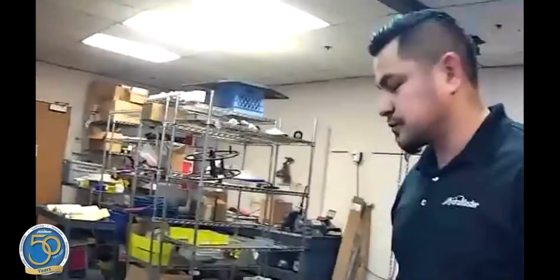Let's talk about some of the reasons why you need to descale. Hard water would be the biggest reason, causing calcium buildup within the system. If your municipal water is higher than 3 grains per gallon, it's recommended to use a water softener to treat the fresh water going into the machine. Water softeners vary, so check with your local distributor on different models and types you can purchase for your system. But yeah, water quality is important.